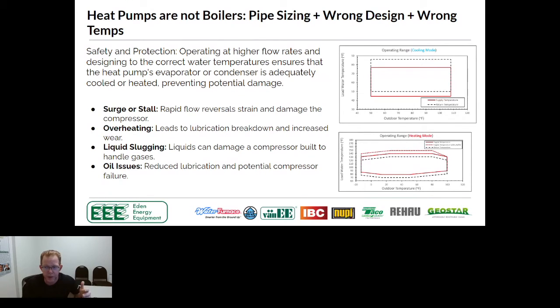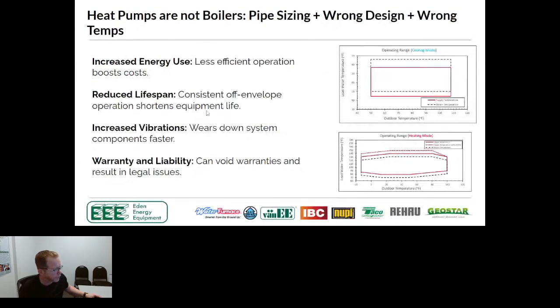The reality is that in most cases when we're going in and putting a hydronic heat pump in, it's going to be a radiant floor system. Maybe there's an air handler on it, but a hydronic heat pump is perfectly paired for a radiant floor system, because typically we're somewhere around 105, 110 degrees. And if you look at this performance table, you can see that 105, 110, 120 is kind of the ideal scenario for an air to water heat pump.